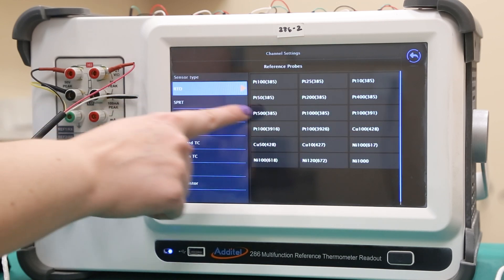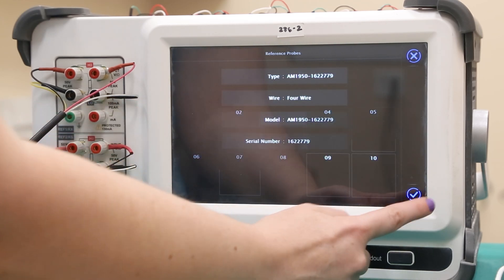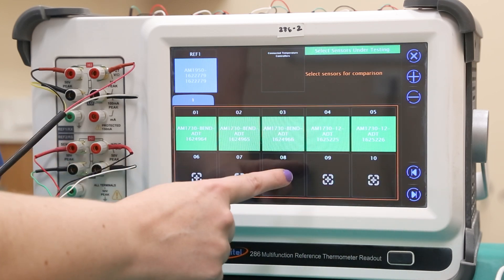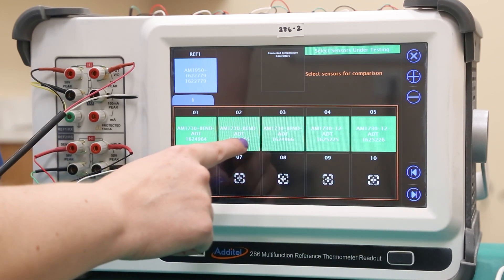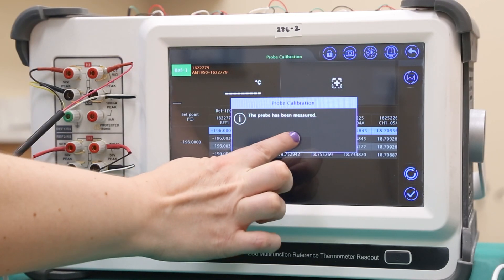First select the type of reference SPRT, connected to REF1. Then select all of the probes, which are connected to ports 1 through 5 on top of the 286. The 286 will once again automatically measure each probe according to the test configuration set at the start of the calibration.